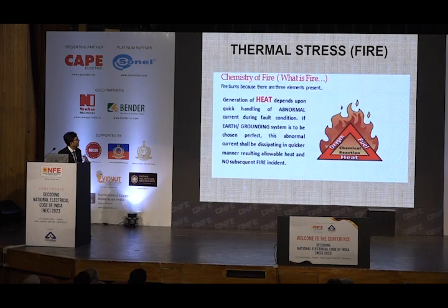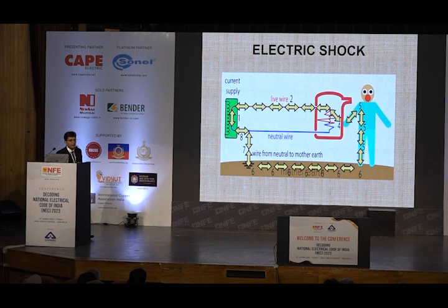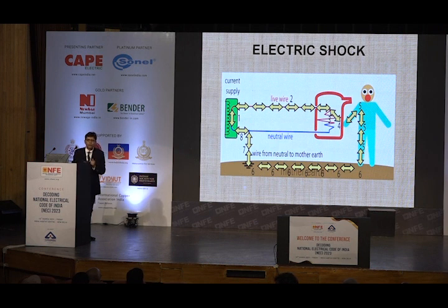When I say thermal stress, when the current starts flowing, there is a heating effect of that current, and heat comes in contact with oxygen, and when some combustible materials are there, one thing is bound to happen, that is the fire. You can't stop it. Then electric shock. If you can provide a dedicated earth path for that fault current to go back to the source, that electric shock also can be avoided.